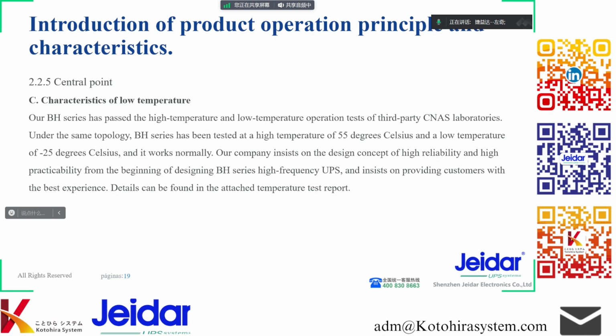Wide temperature characteristic. Our BH series has passed the high temperature and low temperature operation tests of third-party CNAS laboratories. Under the same topology, the BH series has been tested at a high temperature of 55 degrees Celsius and a low temperature of -25 degrees Celsius, and it works normally. Our company insists on the design concept of high reliability and high practicability from the beginning of designing the BH series high-frequency UPS, and insists on providing customers with the best experience. Details can be found in the attached temperature test report.